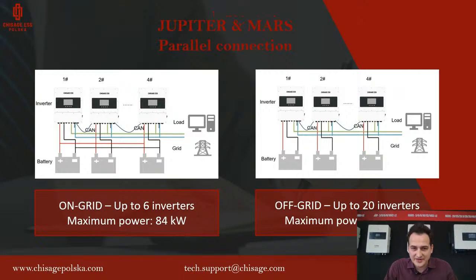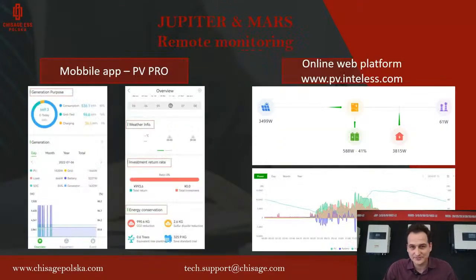For the Jupiter and Mars, as I said, we can connect them in parallel. So 6 inverters in on-grid mode, 20 inverters in off-grid mode. So the maximum on-grid power is 84 kilowatts. We calculate it like this: Mars 14 is the maximum power, multiplied by 6, so 84 kilowatts, and with 20 inverters we can have an off-grid installation with 280 kilowatts. About how to connect this in parallel, I will tell you later.